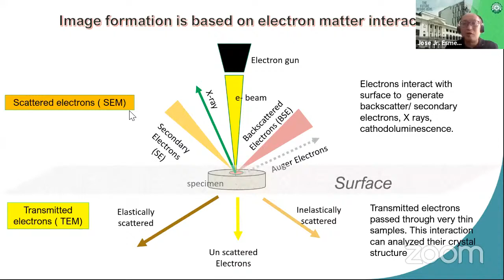So that's why the scanning electron microscope is a surface analytical instrument, while the transmission electron microscope is a transmission analytical instrument. That's why it's called scanning, okay, because it scans on the surface. On that surface, the electron beam scans, and that scanning produces the interaction. When the electron beam hits the surface, it creates these different types of interactions and scattering. So that's the key point in generating the image of electrons. So this part is on the surface and this part on the transmission. It's more like structure.